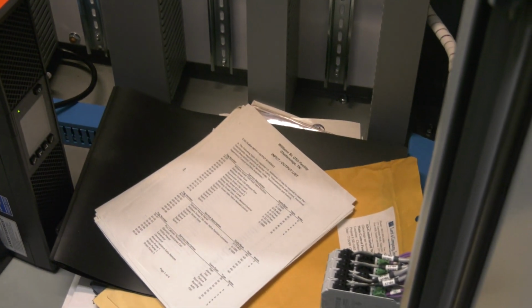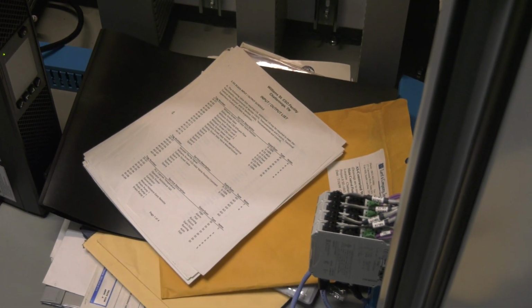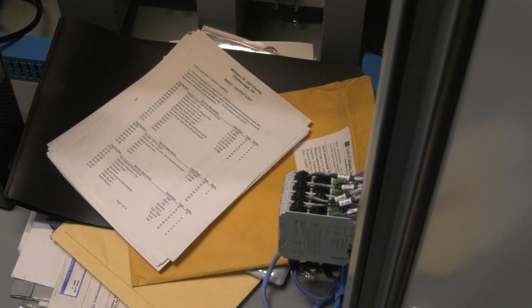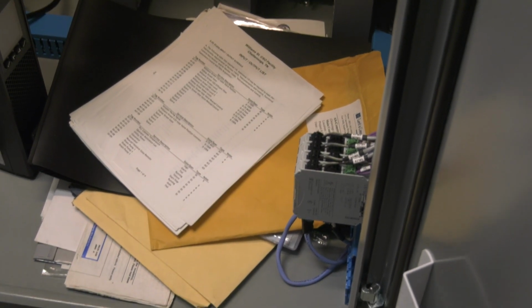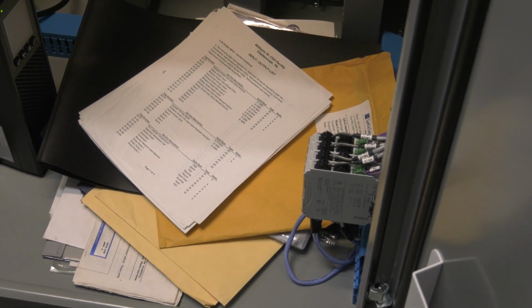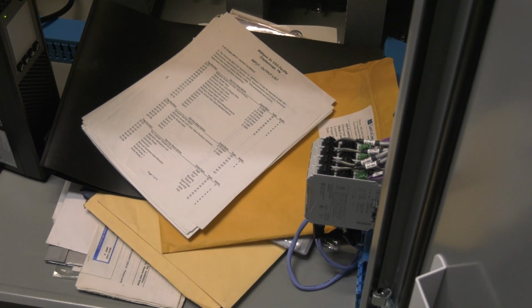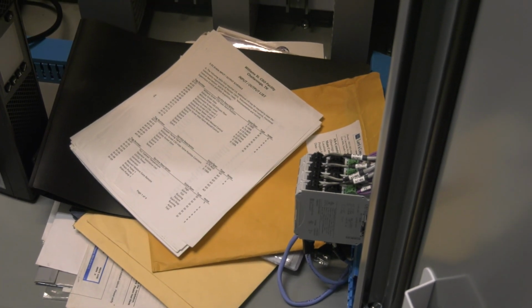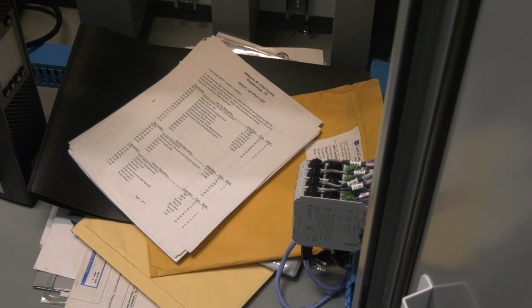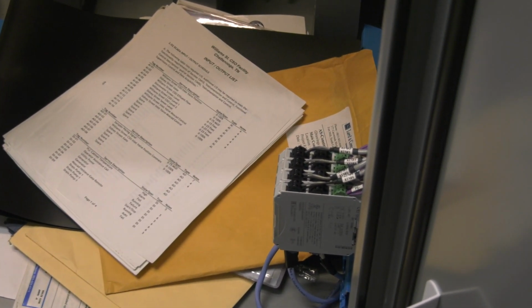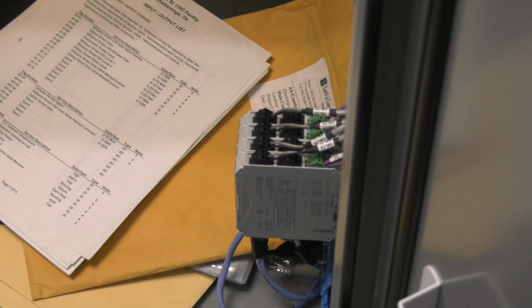And again, we got our intrinsically safe barriers down there. You shouldn't have any problems with that, but if you do, there's no dip switches or anything that need to be set. You just replace them, wire it back up, and you're good to go. And if they have to be replaced, the terminals actually pop out, so you don't have to rewire it. You can just pop all the terminals off of the base, put your new intrinsic barrier in, and plug your terminals back in. You're good to go.